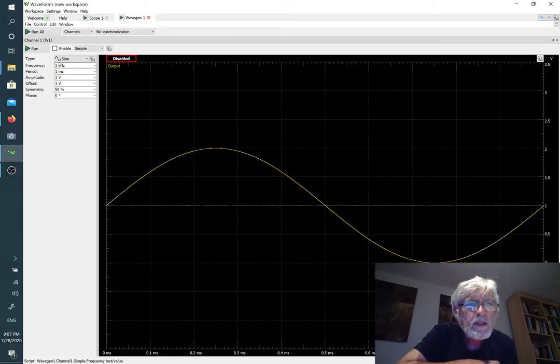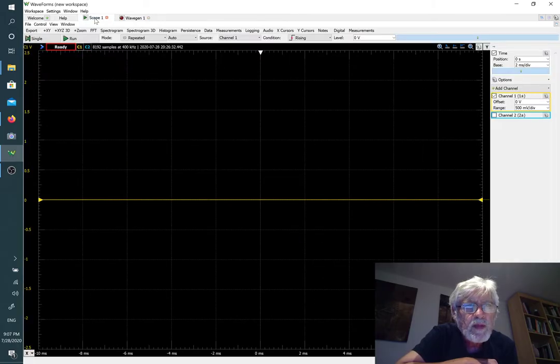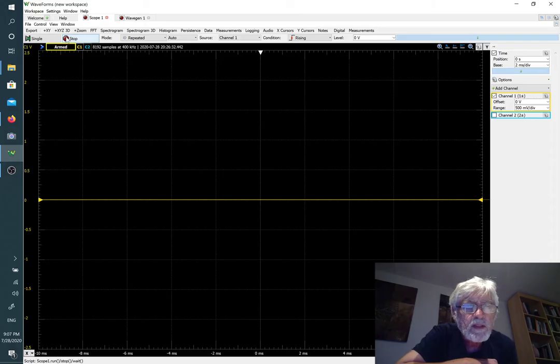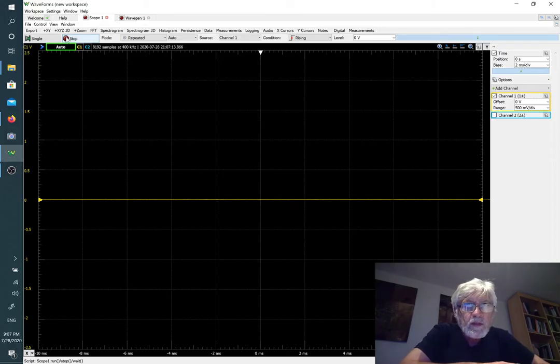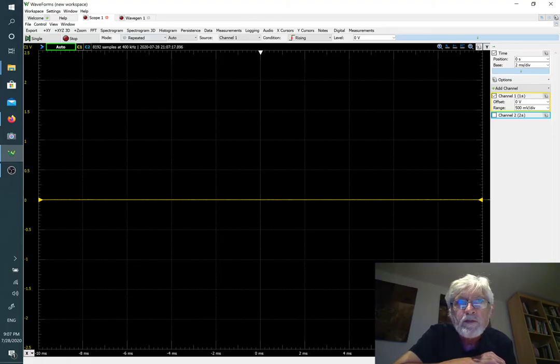I can start that using the run button, and then I can go back to the oscilloscope and get that one to run. We don't see anything yet because I have not connected the wire, so let's go back to the flywire assembly.